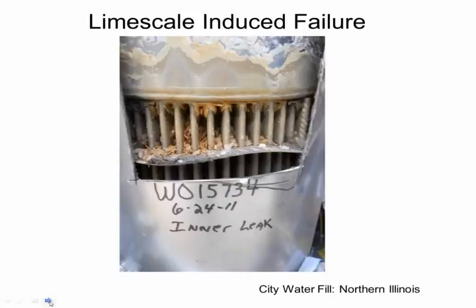So this next shot is what the effects of scale can do, limescale. This is a section out of a condensing boiler, a very high-quality condensing boiler that's come to basically limescale buildup. This is a fire tube boiler with the section cut out so you can see the effects. So fire, flame comes down into these tubes in a downward fashion, and then in the inverse direction, water comes up. It gets routed by these baffle plates, basically to optimize the pickup of heat by the water. And you can see the limescale buildup. Now, theoretically, if this heat exchanger builds up uniformly with limescale, perhaps you might not have had a failure, maybe a heat penalty, but not a failure.